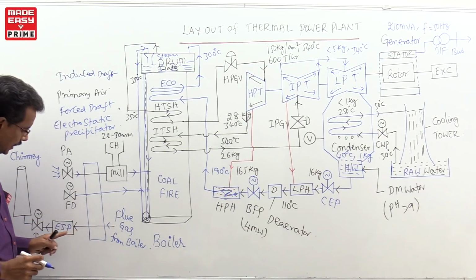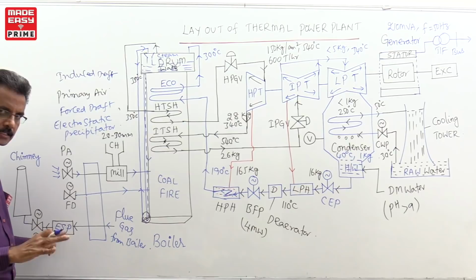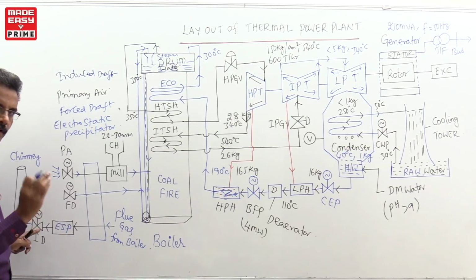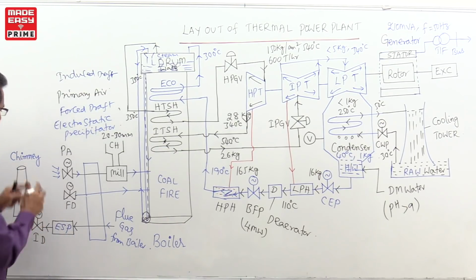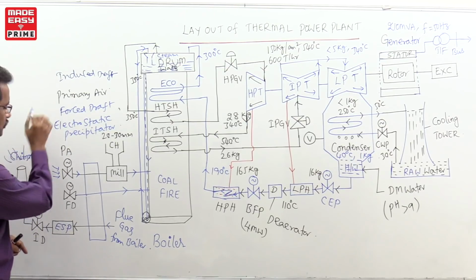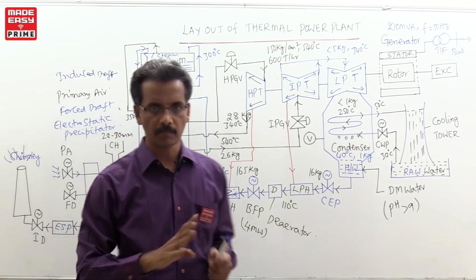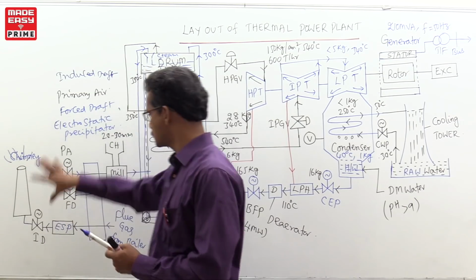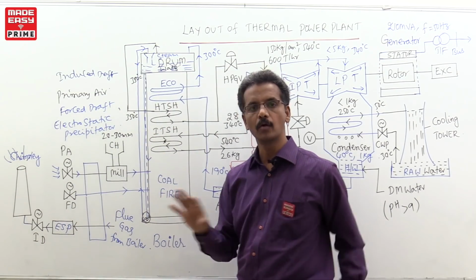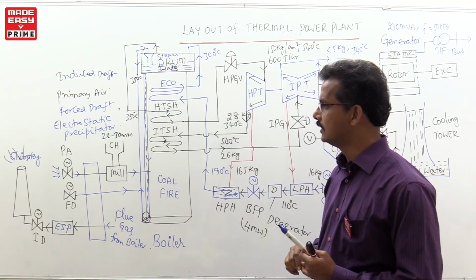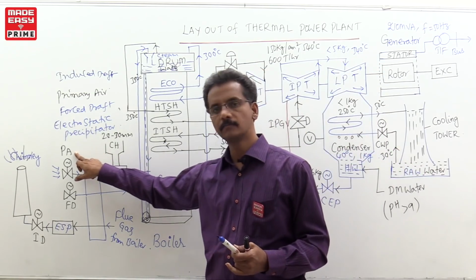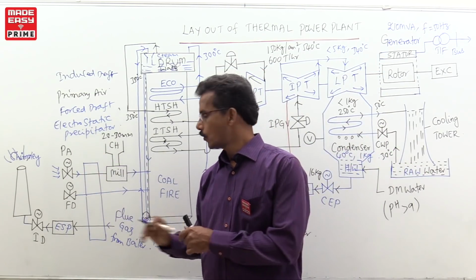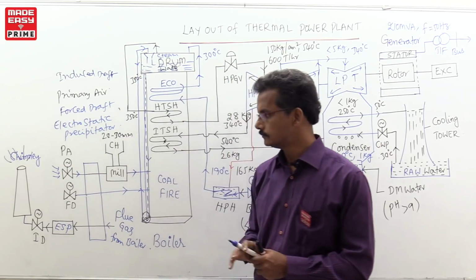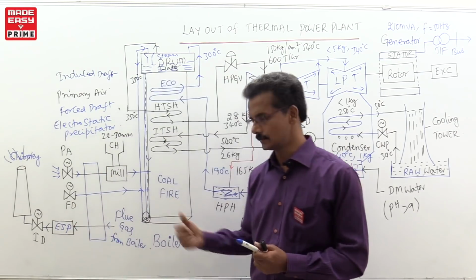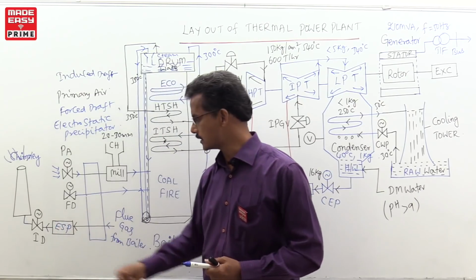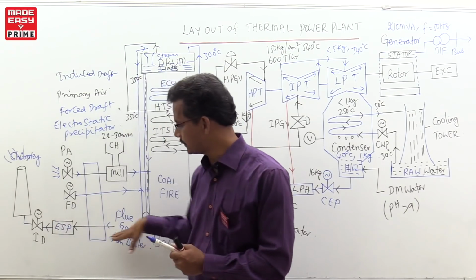The induced draft fan is used to draw the flue gases from the boiler, and the ESP is used to remove the ash particles. After the ash particles are removed, the flue gases are released to the chimney, so they are released to the atmosphere through the chimney. These are the extra components we have to use in thermal plants. The primary air fan conveys the coal powder from the mill to the boiler. The FD fan supplies the oxygen. The ESP collects the ash particles. The ID fan extracts the flue gases from the boiler.